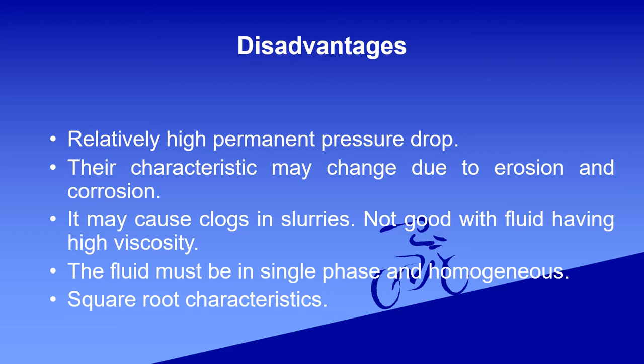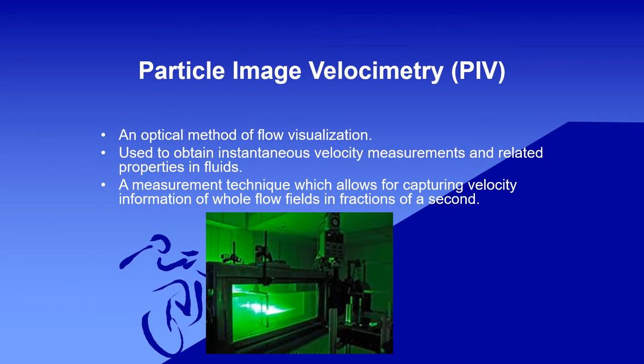It has five disadvantages: high permanent pressure drop, characteristics may change due to erosion and corrosion, may cause blockages in slurries, fluid must be in single phase and homogeneous, and the last one is square root characteristics.